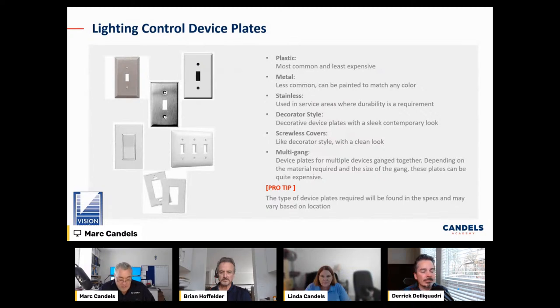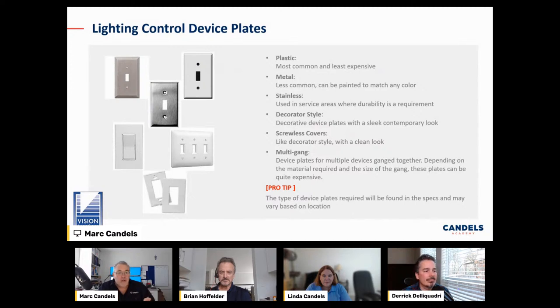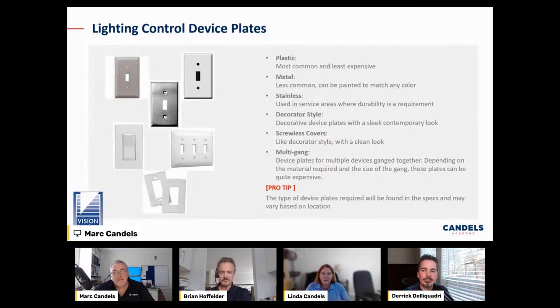A pro tip: read the specs to know what kind of devices they're calling for, especially device plates. We have plastic plates, metal plates, paintable plates, stainless steel, Decora decorator style, and the really expensive ones like Lutron or screwless covers — those are pricey. And don't forget multi-gang switches. Brian always advocates counting your one-gangs, two-gangs, and three-gangs carefully. If you've got a two-gang switch, you have two single poles in that box, plus a two-gang plate.